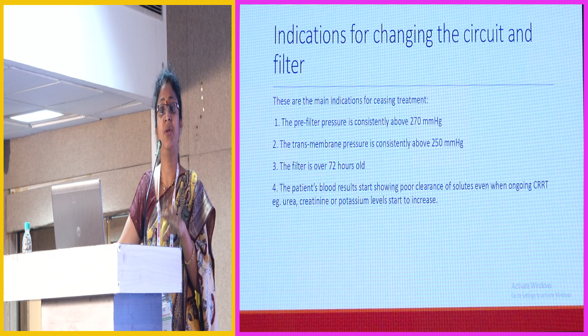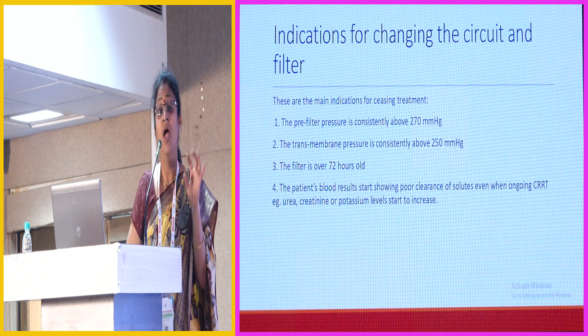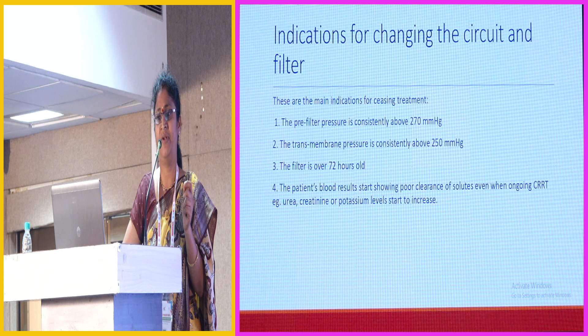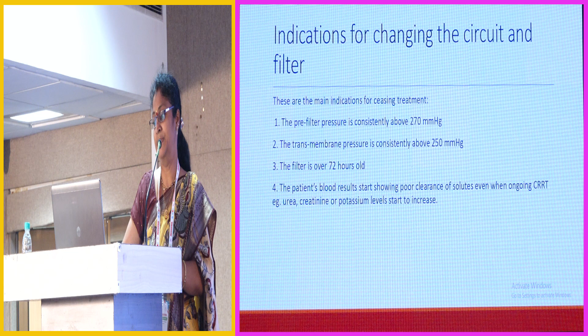And the last sentence is very, very important. Though the filter is not clotted and you are not getting any alarms, if the patient's blood results start showing poor clearance of the solutes, even while the CRRT is ongoing, that is urea, creatinine and potassium levels, it is the time to change the filter. I learned this lesson during my practice as an assistant professor in SWIMS, because the majority of dialysis patients get thrice weekly dialysis, but when we check the labs, their hemoglobin is not good, their general well-being is not good, their nutrition is not good, but they tell us they are getting 4 hours of dialysis. That is not so; a lot of recirculation might have been happening in the fistulas. What you are giving is not important, what the patient is getting is important. This is where we need to change the filter. These numbers are only to guide us as a monitor, but we don't rely completely on the numbers.